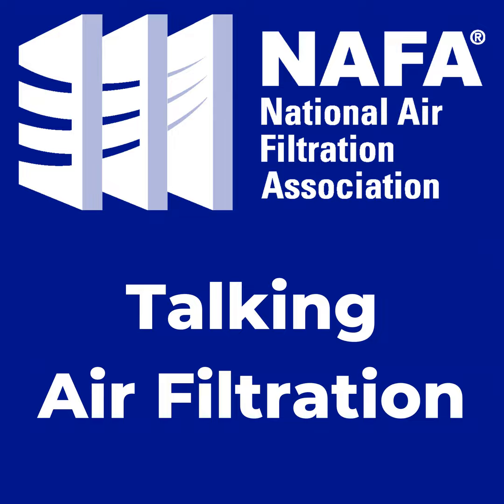And that's going to cause an issue with how the filters are tested. In ASHRAE dust, you put cotton linters in there. So you're putting even more big particles in with the ISO fine dust, and you're exacerbating the issue, basically. So I think if we have a better way of testing filters, it could be more favorable to showing how nanofiber medias actually perform, and then we can get more traction on that in the industry.